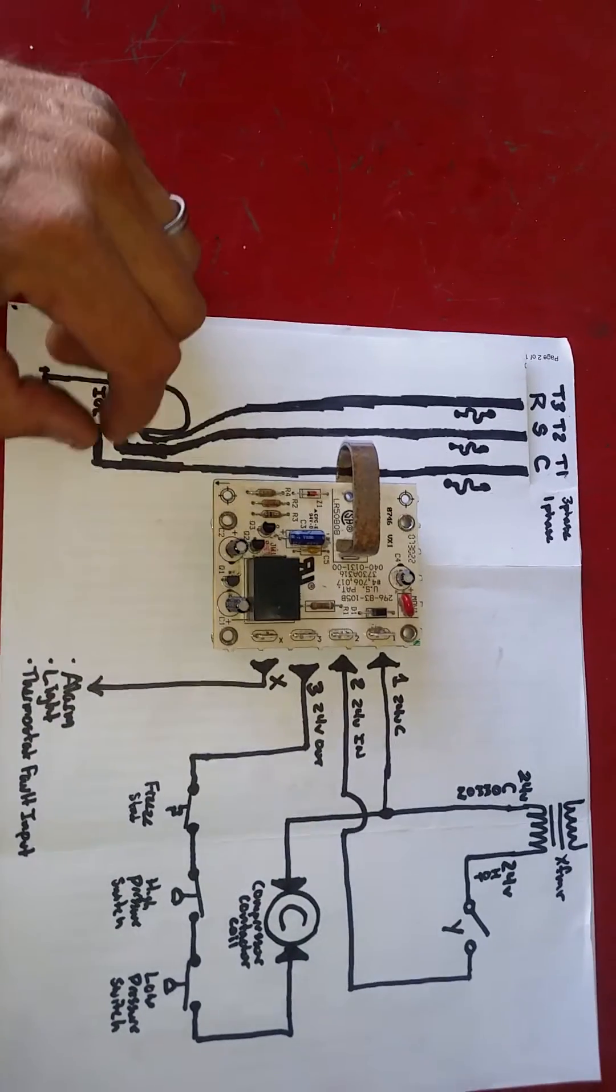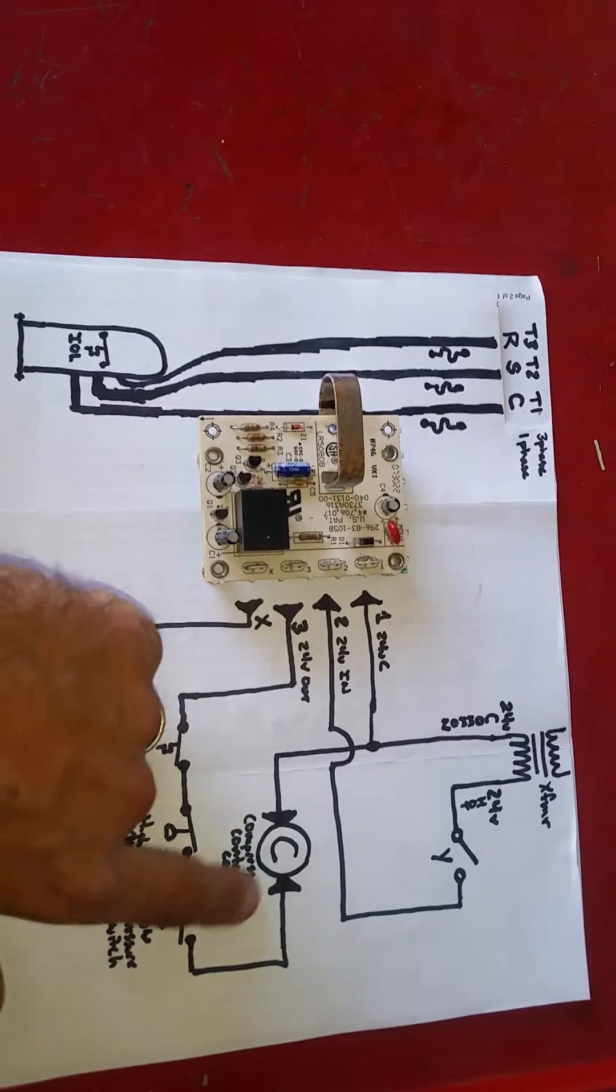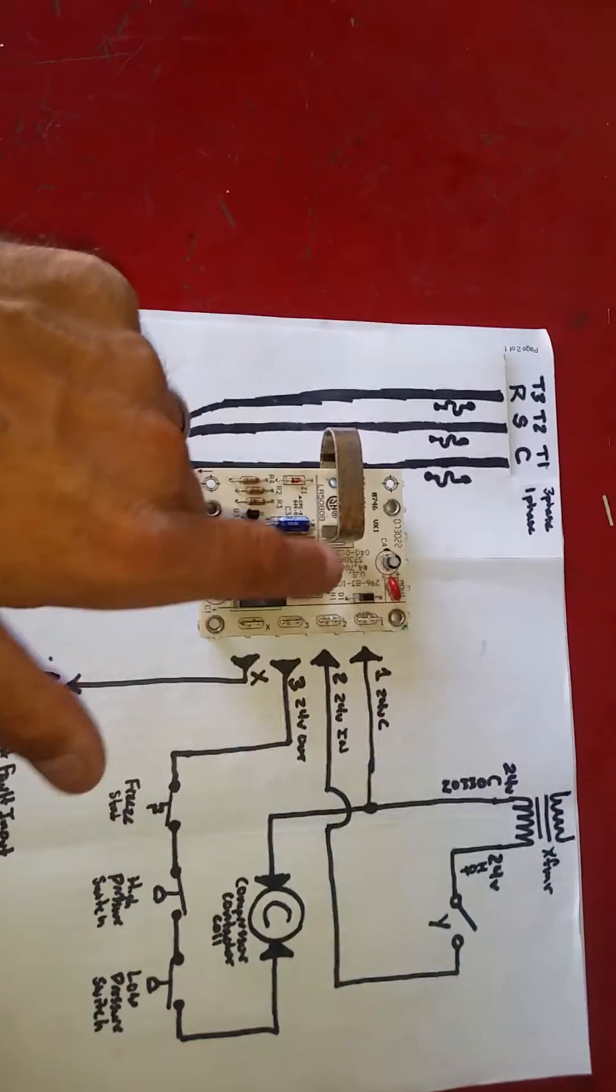If the internal overload opens, compressor shuts down, no current, lockout condition. I think there's a misconception that there's a safety loop to this. There's not.